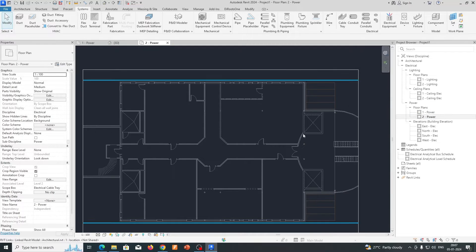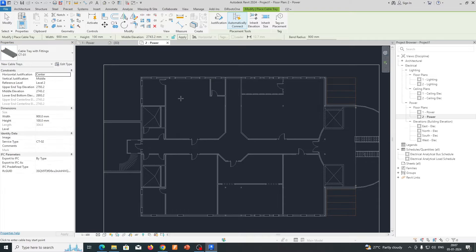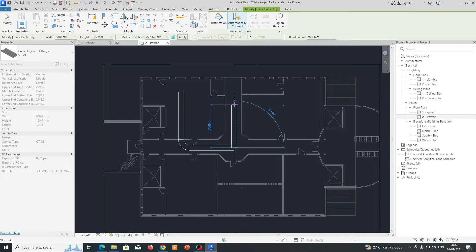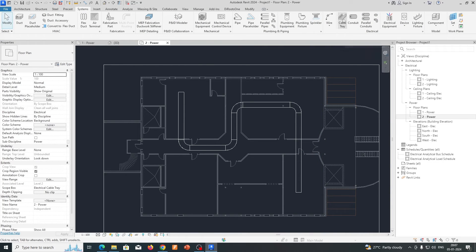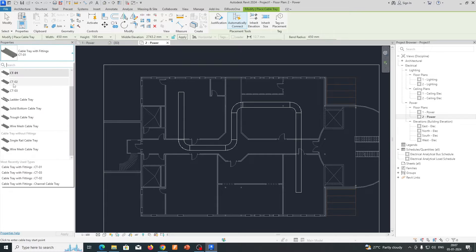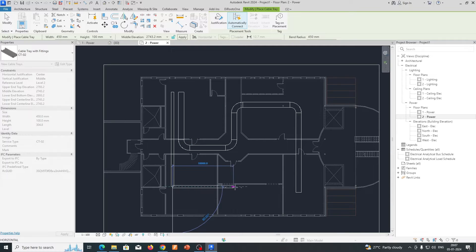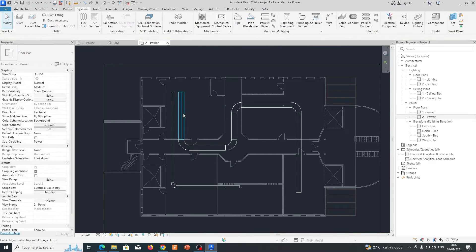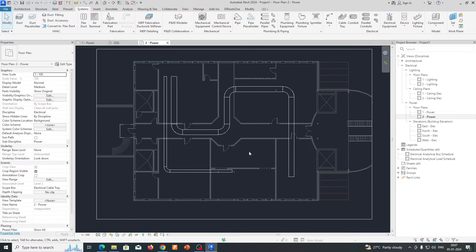Now go to the second level. Here also we need to create some cable trays. First I'm creating CT01 and drawing it like this wherever needed. Then placing another cable tray on Level 2 at 450mm — that comes out as CT02. Give it the service type CT01 so you can easily identify it when making schedules and quantities.